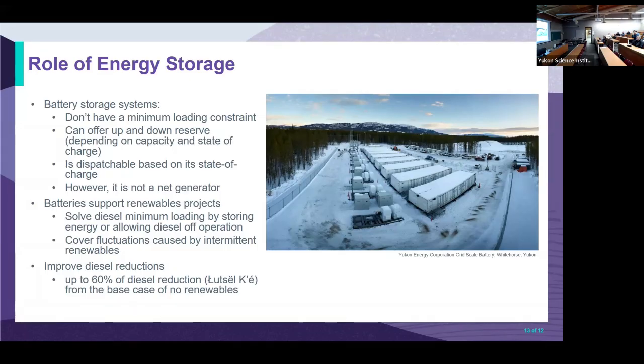That's a little different from how diesel generators work. Diesel generators have a max size, and we can only run them within a certain rated capacity—we can't go below a minimum loading constraint. But with a battery, we can run it whenever we want. Whereas with a diesel generator, if we start getting to its max loading, we have to turn on a second generator, and before that first generator peaks, we have to make sure the next one is ready to pick up the load.